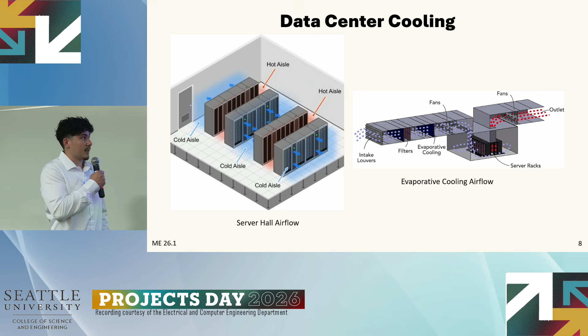One of the types of air cooling used today is evaporative cooling. Air is brought in from the outside using fans, and then it passes through an evaporative pad, which is fed water with a motor. When the water evaporates, it takes heat from the air, cooling the air before it goes into the server halls.